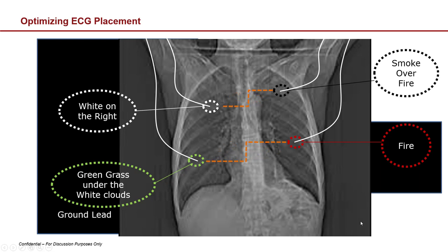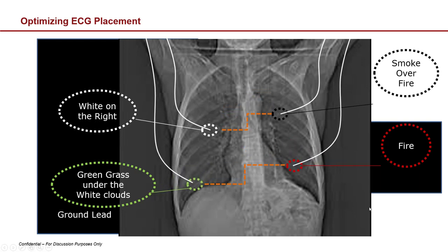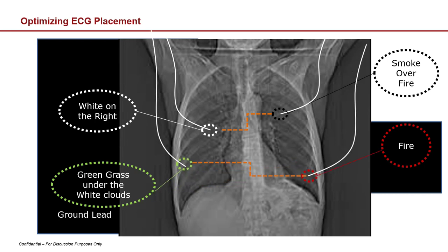It's important to get a good signal. For lead placement: white on the right, black smoke over red fire on the left, and green grass (the ground lead) underneath the white one. Try to triangulate the heart and keep leads offset to reduce beam hardening from metallic clips. If leads don't work, adjust them — the closer to the heart, the better the signal. Never put leads on the stomach; only put on the arm if there's a pacemaker causing interference.